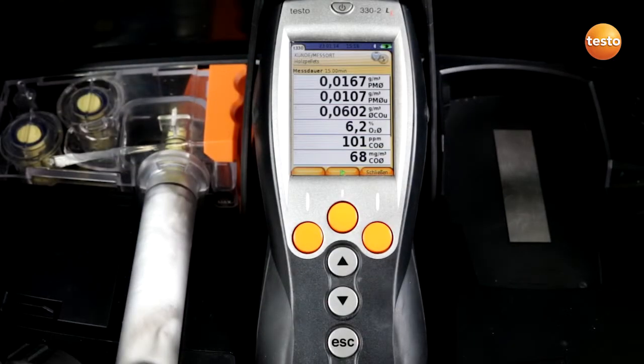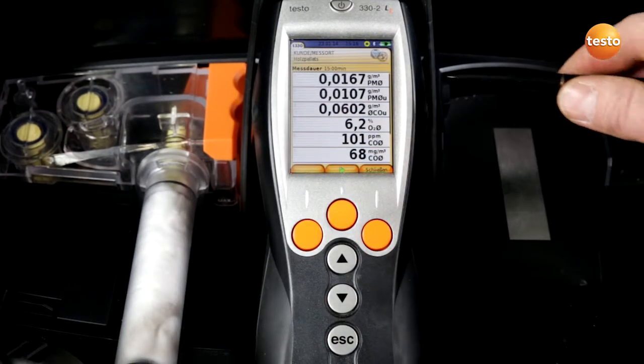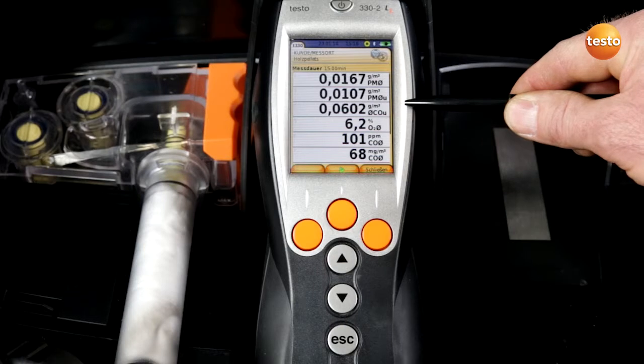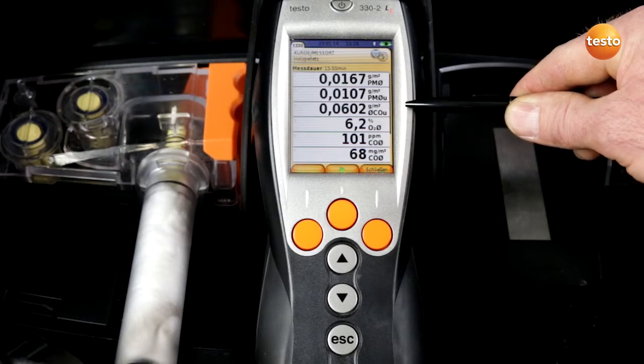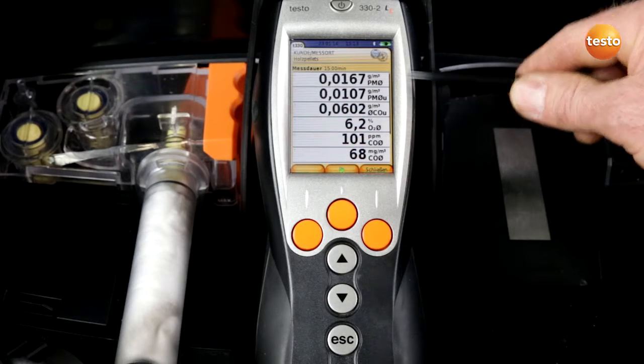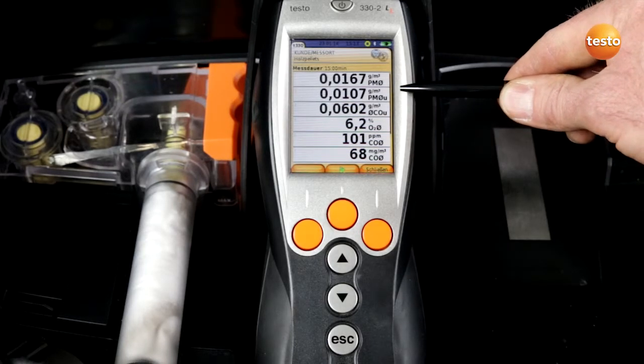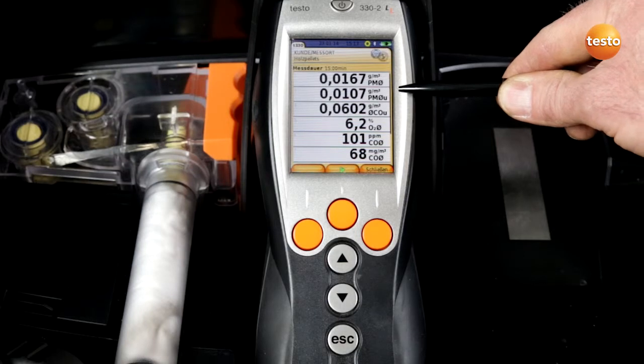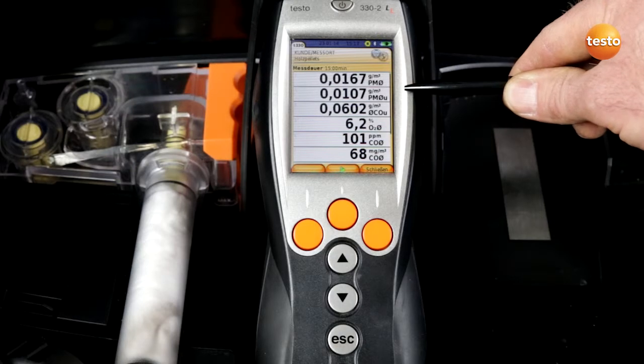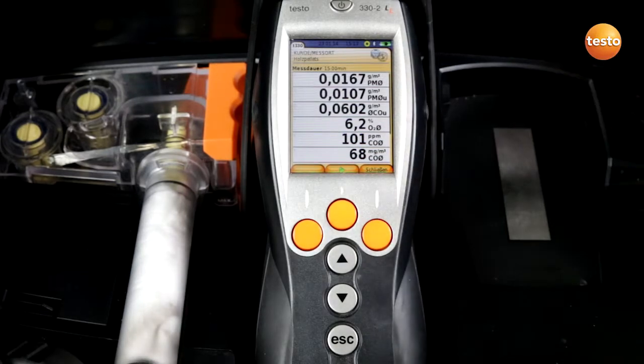The measurement values after the 15-minute measurement duration can now be read off. The Federal Emission Control Law prescribes 2 limit values. The CO content in grams per cubic meter, which we can read here. The tolerance has already been subtracted. The limit value for this system is 0.8 grams per cubic meter. As we can see, it's OK. The particle content can be read off here in grams per cubic meter. The tolerance has already been subtracted here too. The limit value for this system is 0.06 grams per cubic meter, and again we can see that the system is burning well.